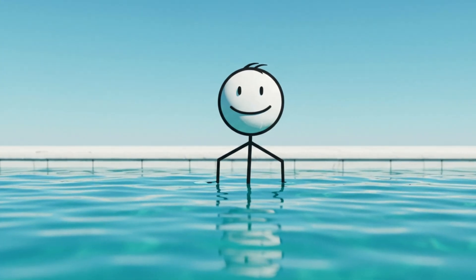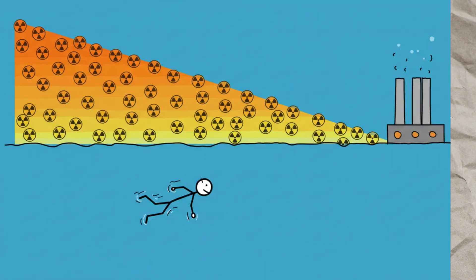Now the pool itself. Temperature: typically between 25°C and 35°C — warmer than most swimming pools but cooler than a hot tub. Radiation is the bigger issue. For the type of radiation given off by spent fuel rods, every 7 centimeters of water cuts the radiation intensity in half.